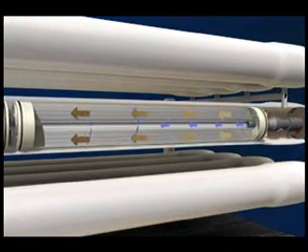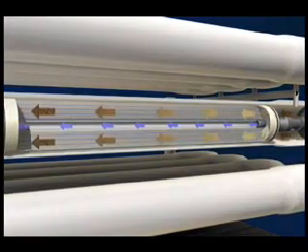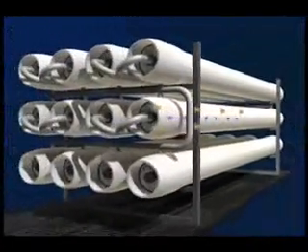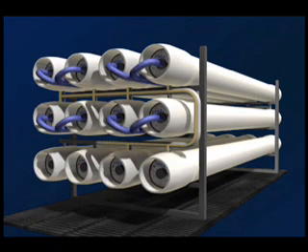The feed water that does not permeate through the membrane becomes enriched in salts as it travels through the feed channel spacer due to permeate water being removed. Typically 8 to 10% of the water is removed in one 40-inch long membrane element.